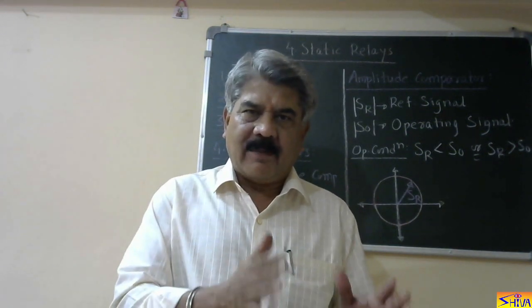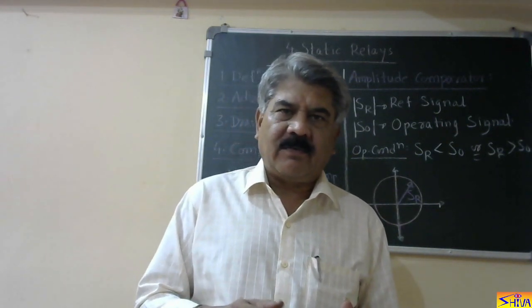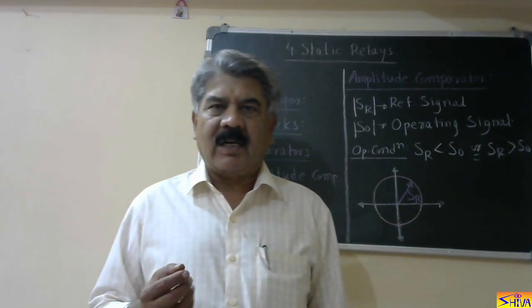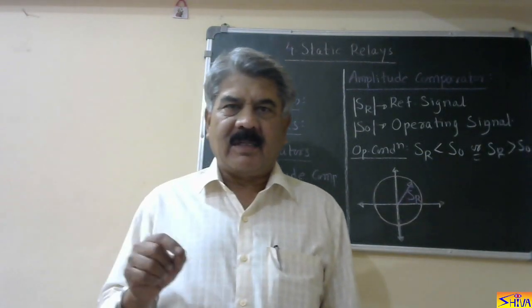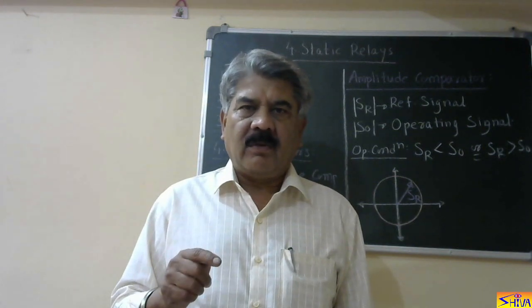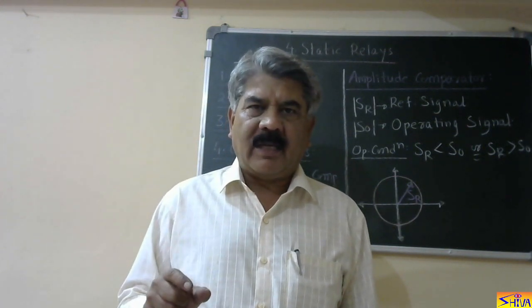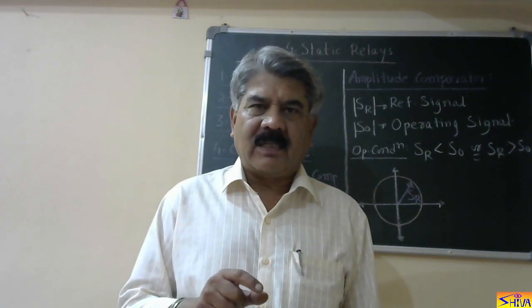So the relays are the same. The operating principle or operating condition is the same. For example, if we consider the overcurrent relay, the operating condition will remain the same. When the relay current becomes more than the pickup value, the relay will operate. This condition can be generated by the electromechanical relay as well as by the static relay.